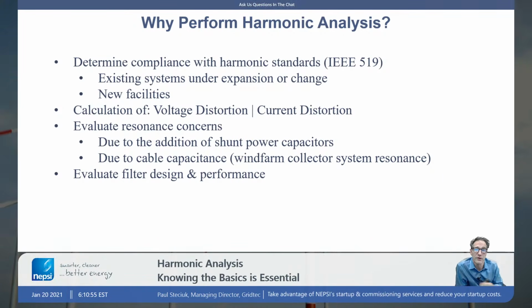We may have to evaluate resonance concerns, another key point. When you install a capacitor bank within a system, you create resonance conditions. We want to make sure that we don't have resonance concerns. When you have resonance, you have high voltage distortion, you have high current distortion, so you therefore have a poor power quality issue. So evaluating resonance is another reason. And then you want to evaluate filter design. Part of harmonic analysis is, I've got a problem, I need to fix it, I'm going to evaluate the filter design. It's an iterative process.